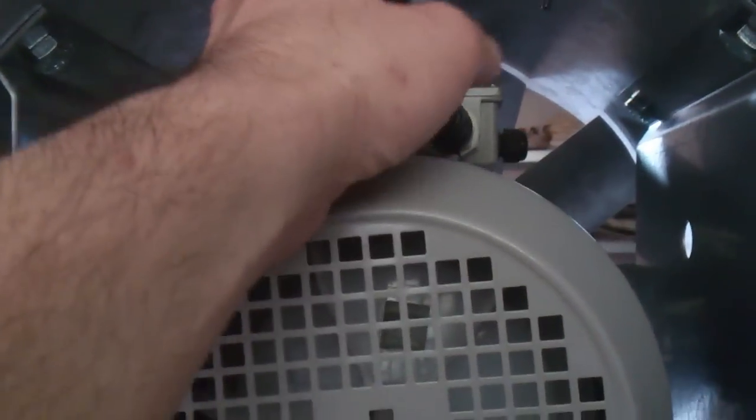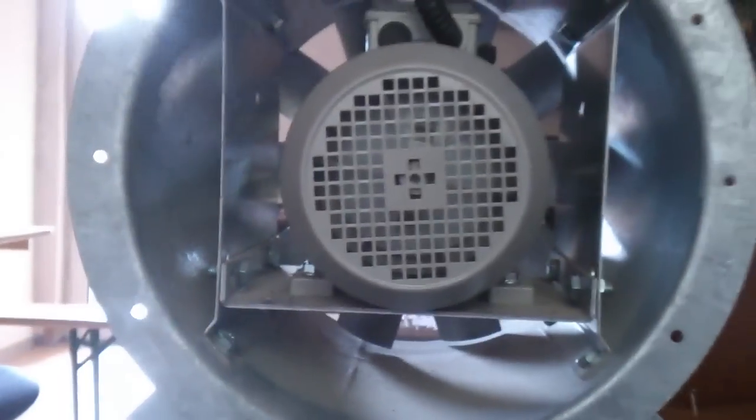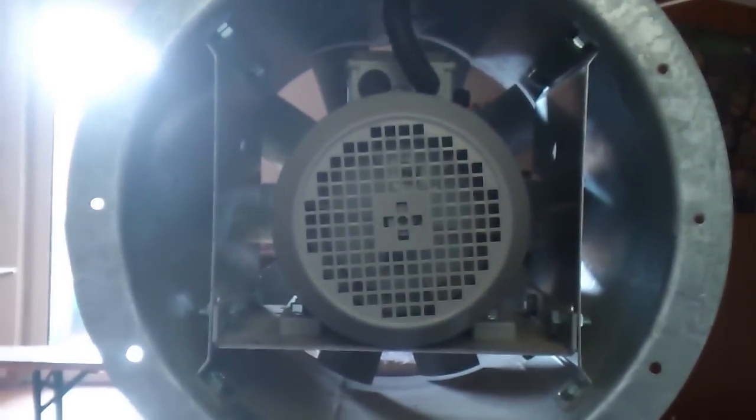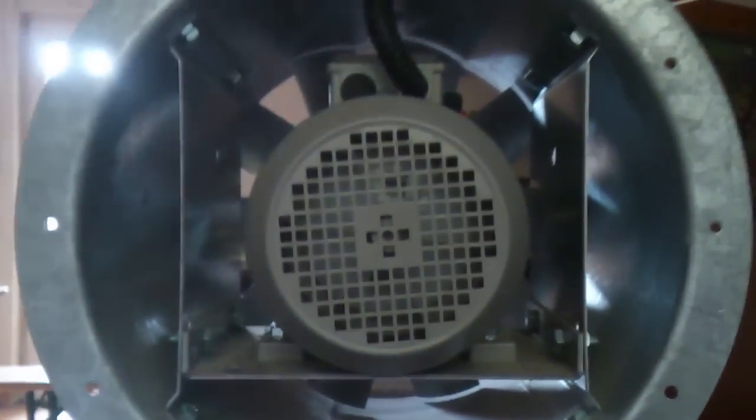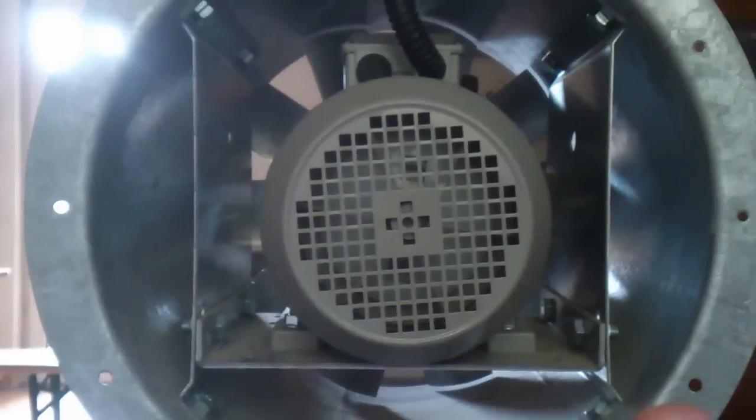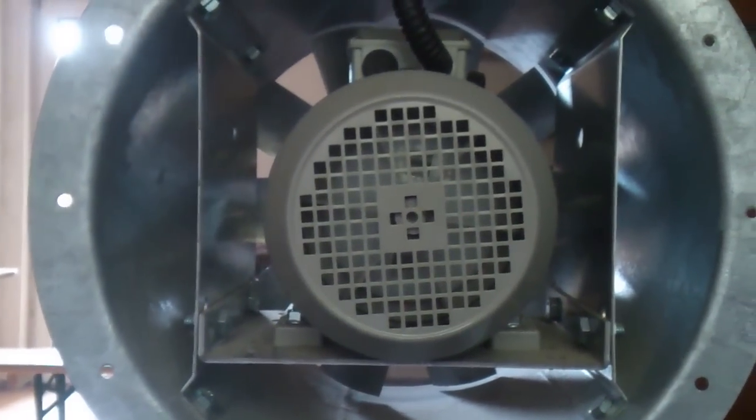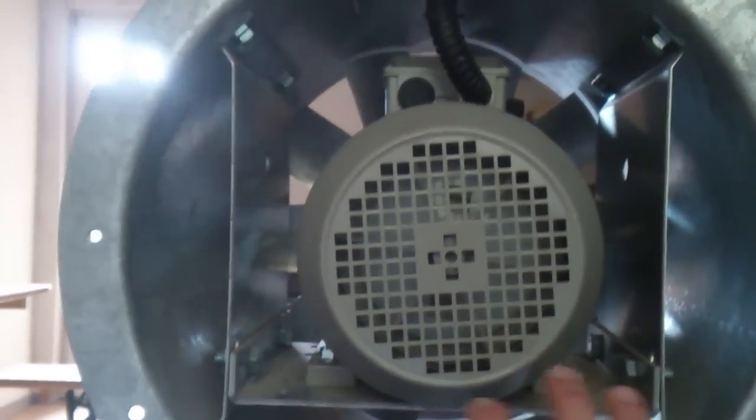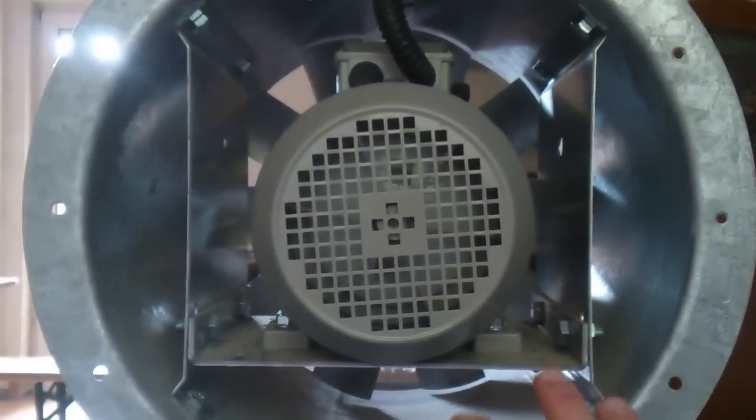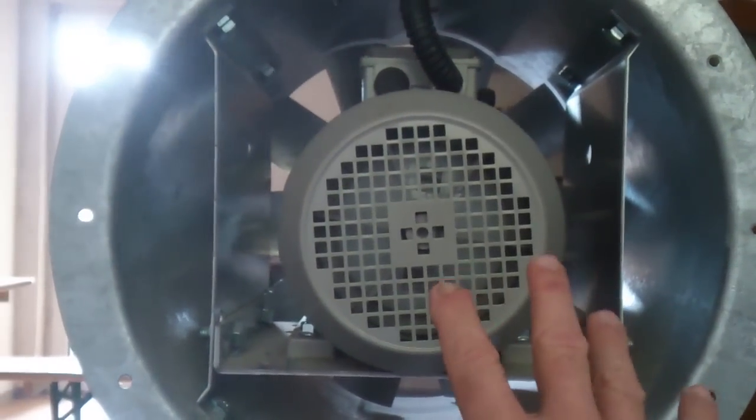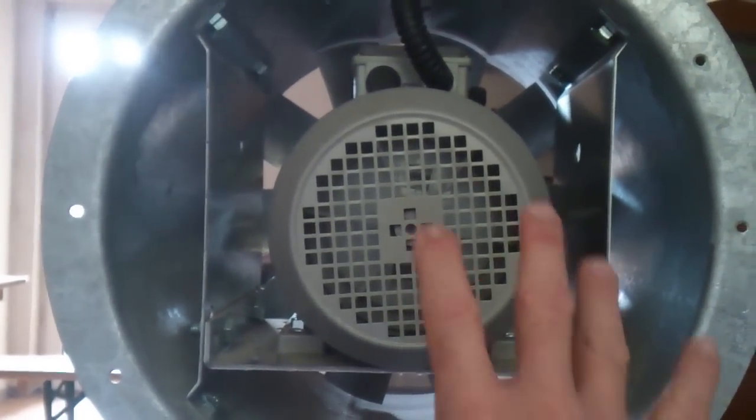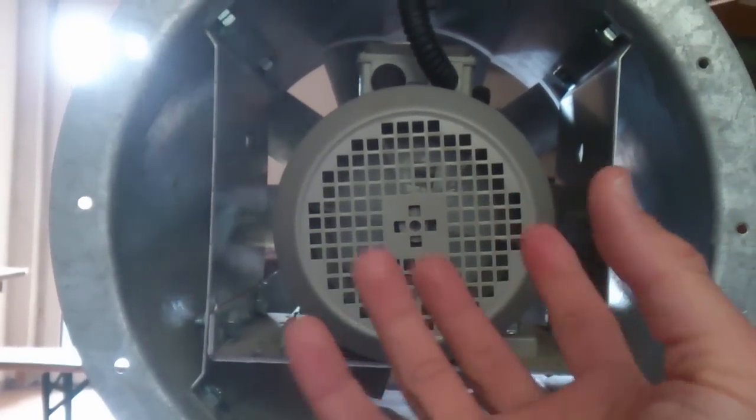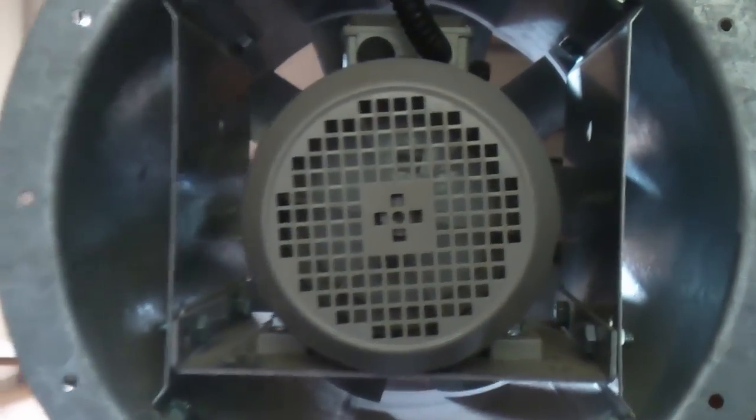In this case, there's a terminal box and that cable going to the external terminal box. You can see how much space the motor and the motor support are consuming. They're really a massive barrier for the airflow.